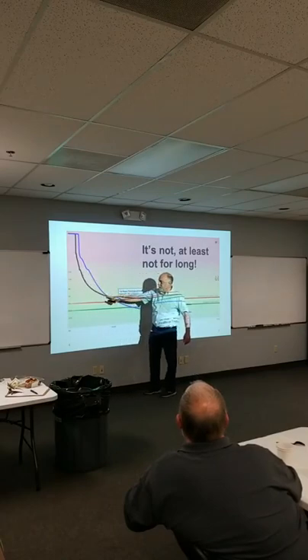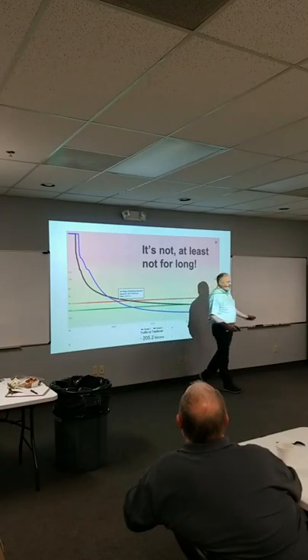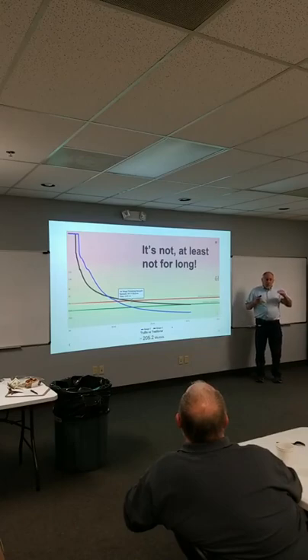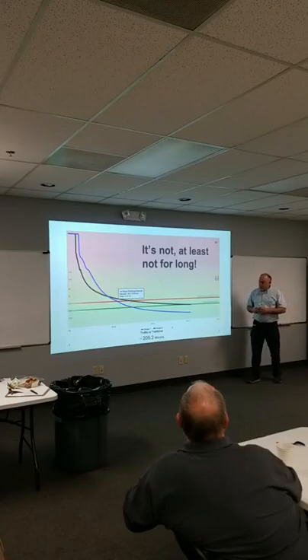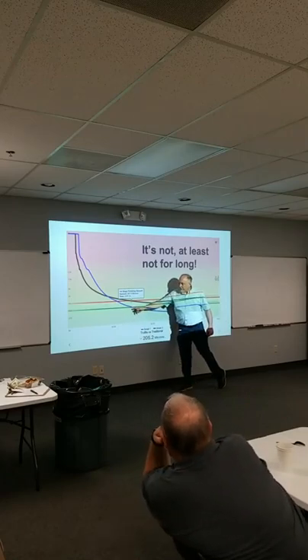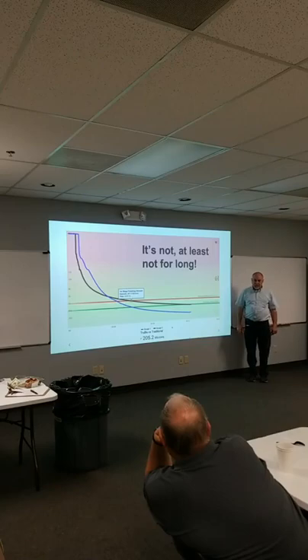It's blowing past till we hit 2,000 microns. At 2,000 microns, something magic happened. The pump was no longer the limiting factor, because the 2 CFM pump was a limiting factor. At 2,000 microns, all of a sudden the hose became the limiting factor. Just switched around. And at 2,000 microns, look what happened here. This is 7 minutes, right?